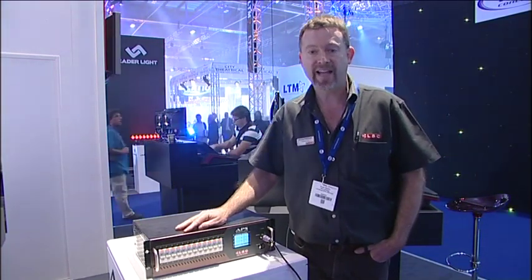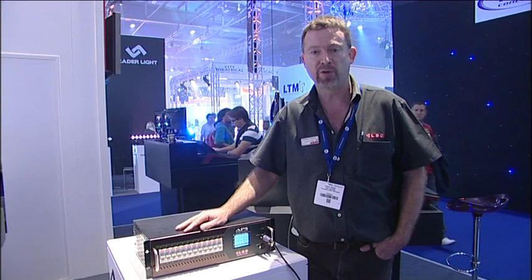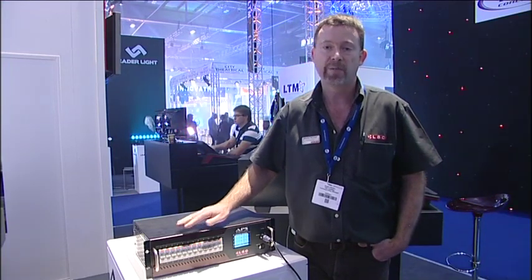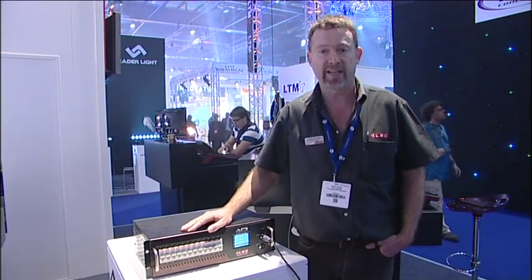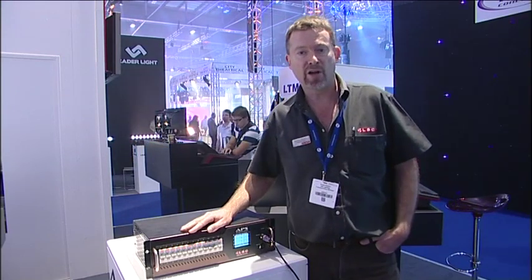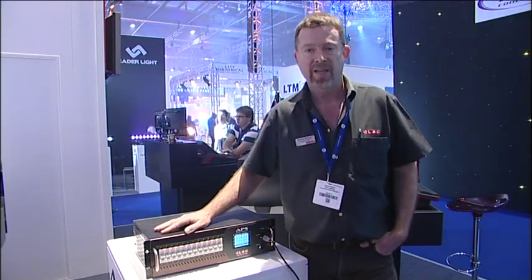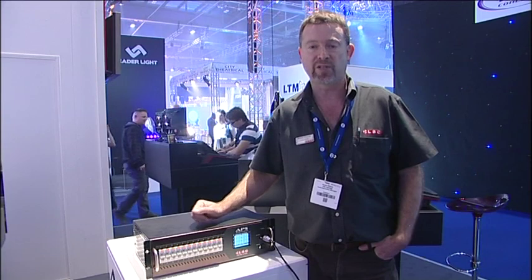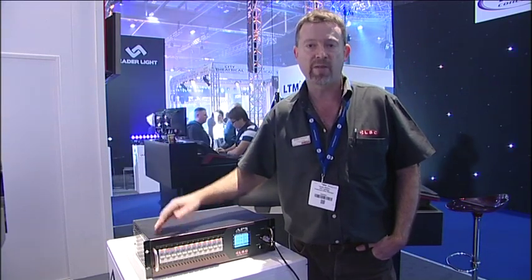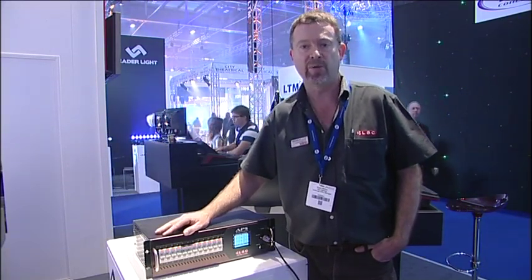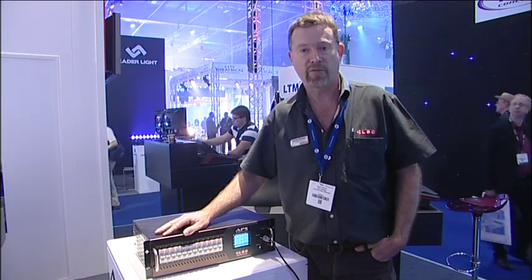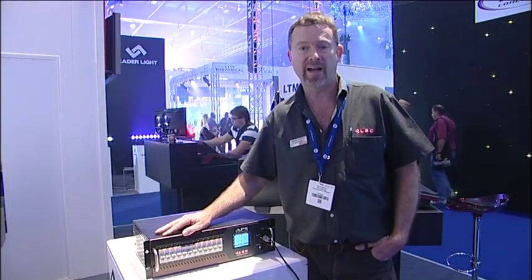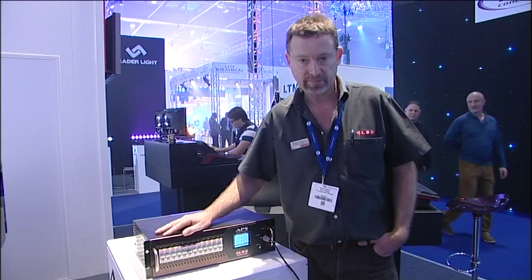We also provide a standalone mode for those occasions where multiple units are used on an installation but are unable to be interconnected by linking cables. In the standalone mode, each unit is given a unit number and that adjusts the time delay on startup so that unit one will start up and then when that is finished, unit two will start up and then unit three. This is ideal for fetes and fairs where all the individual market stalls require power.